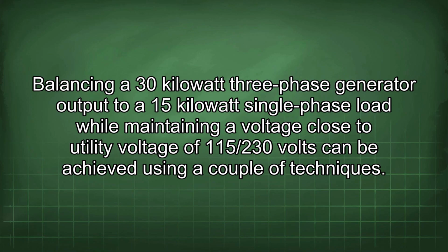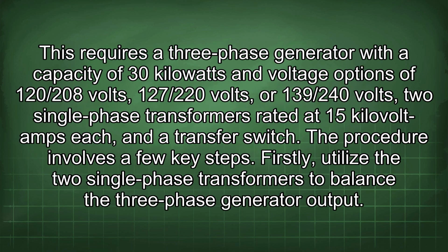Balancing a 30 kilowatt three-phase generator output to a 15 kilowatt single-phase load while maintaining a voltage close to utility voltage of 115/230 volts can be achieved using a couple of techniques. This requires a three-phase generator with a capacity of 30 kilowatts and voltage options of 120/208 volts, 127/220 volts, or 139/240 volts, two single-phase transformers rated at 15 kilovolt amps each, and a transfer switch.